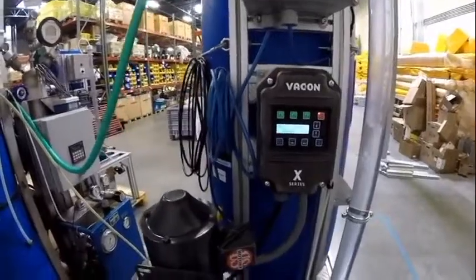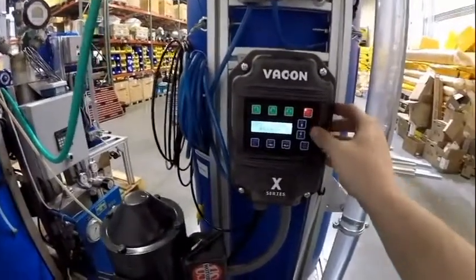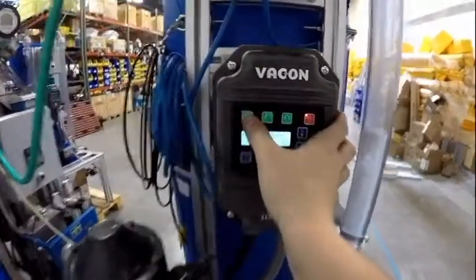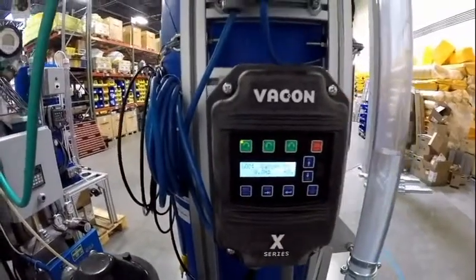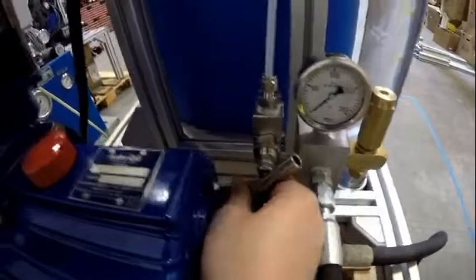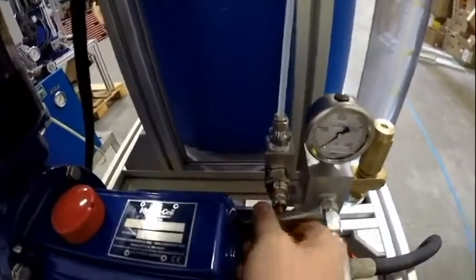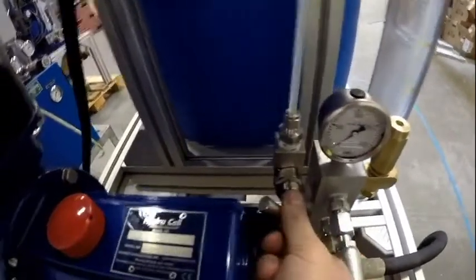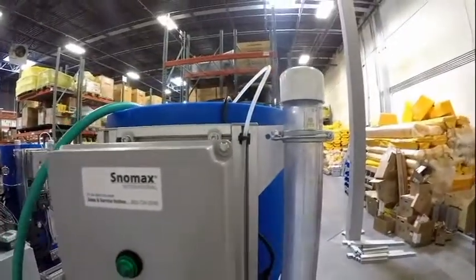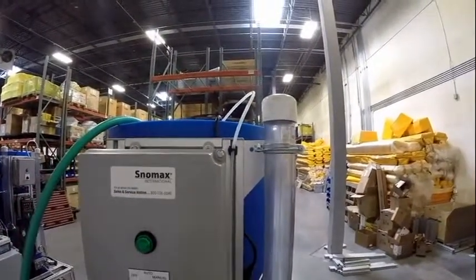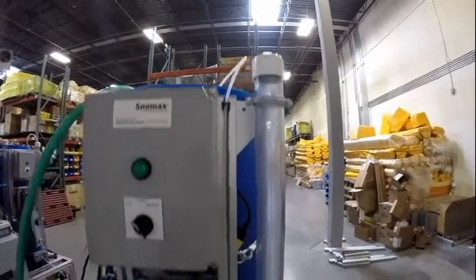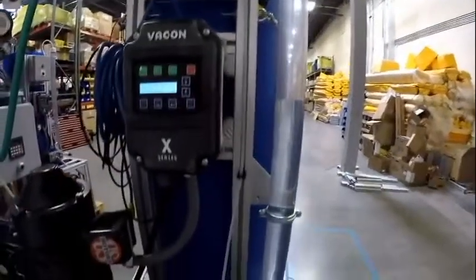Then what we'll do is to turn the system on with the green forward arrow on the VFD. Then we'll open the bypass valve to make sure all the air is out of the system. You may see some air bubbles flowing up to the tube, back into the tank. Once you get a solid flow of water, you can close the valve.